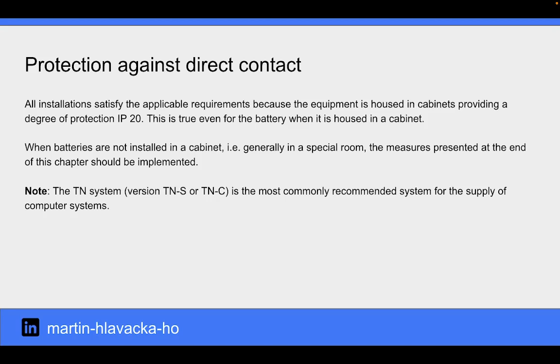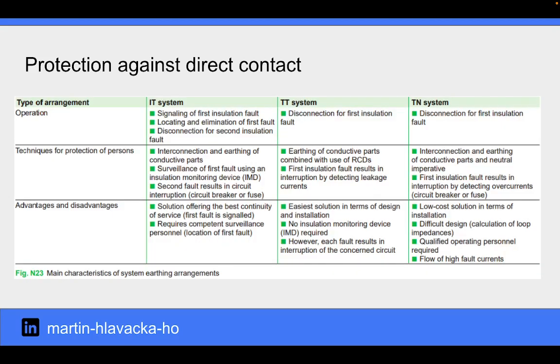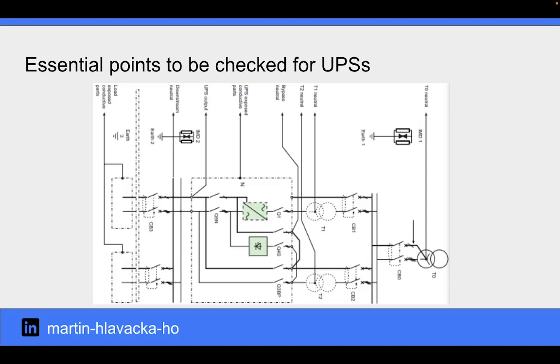All installations satisfy the applicable requirements because the equipment is housed in cabinets, providing a degree of protection IP20. This is true even for the battery when it is housed in a cabinet. When batteries are not installed in a cabinet, certain measures should be implemented. On this slide, you can see a table with the main characteristics of system earthing arrangements. On this slide, you can see a diagram that shows all the essential points that must be interconnected, as well as the devices to be installed to ensure installation conformity with the safety standards.